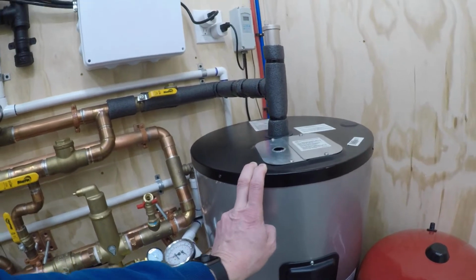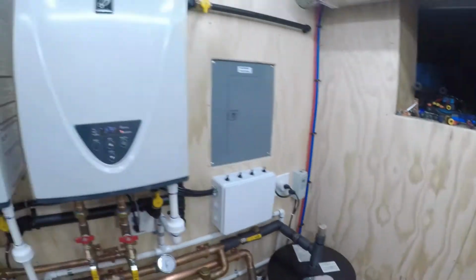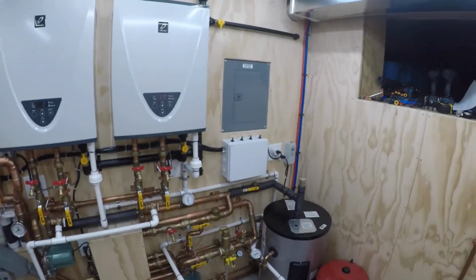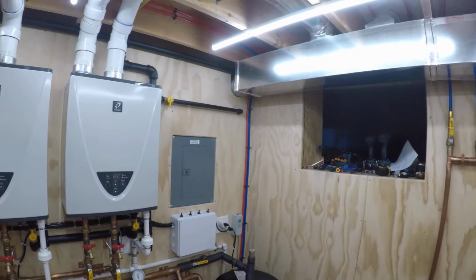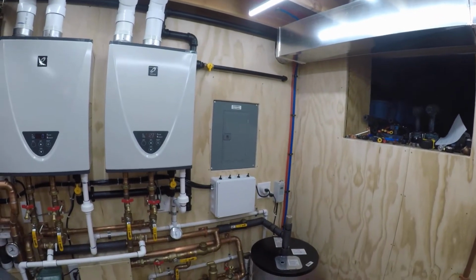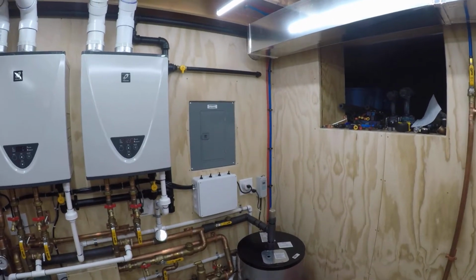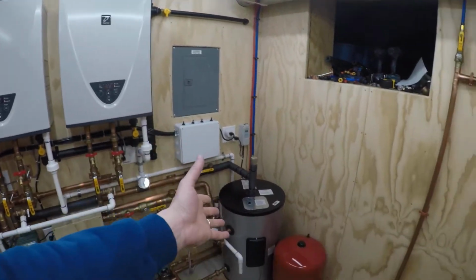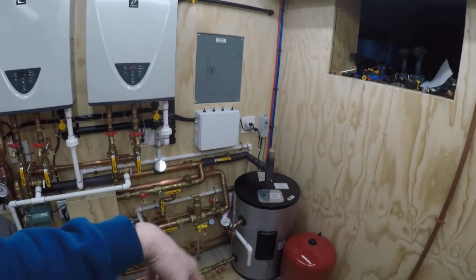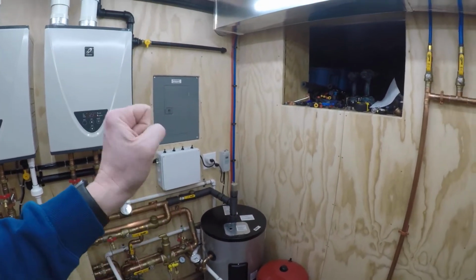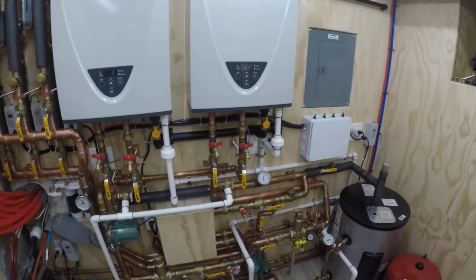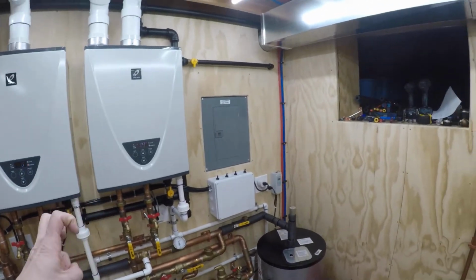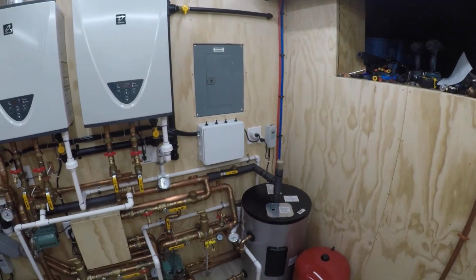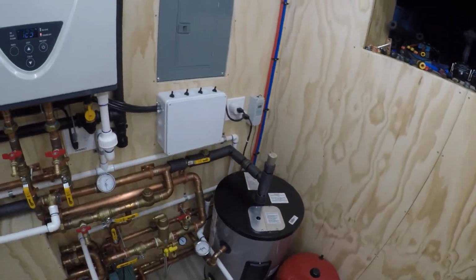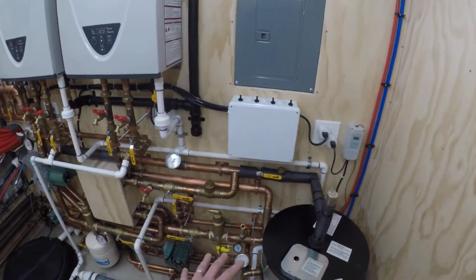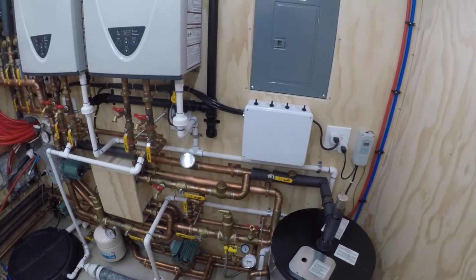As long as you're not exceeding 7.6 gallons a minute, which would be 2-3 showers on at the same time, the tank will catch up. The system will eventually beat the use that you're drawing from it. So in other words, you can't run out of hot water, so to speak. I don't know if that makes sense, but that's kind of how that part of it works.